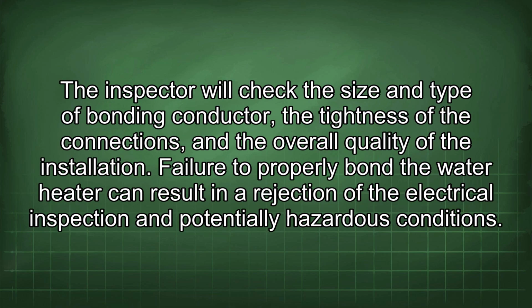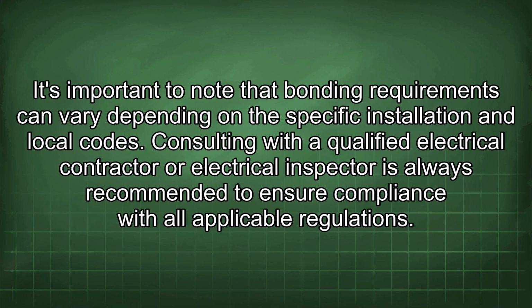requirements. The inspector will check the size and type of bonding conductor, the tightness of the connections, and the overall quality of the installation. Failure to properly bond the water heater can result in a rejection of the electrical inspection and potentially hazardous conditions. It's important to note that bonding requirements can vary depending on the specific installation and local codes. Consulting with a qualified electrical contractor or electrical inspector is always recommended to ensure compliance with all applicable regulations.